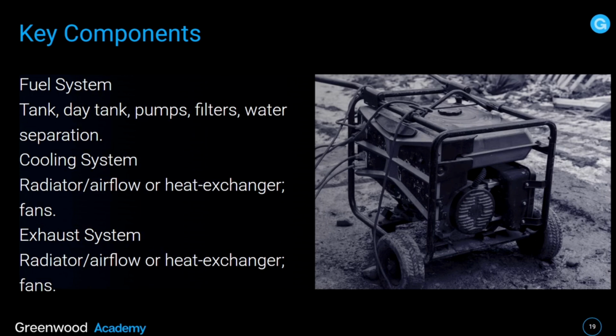Now, all these things have to be taken into consideration. One, when selecting what is the most effective GENSET for your application. And two, the most effective GENSET also depends on where it's going and where the exhaust is actually going. It's a really important point, especially when it comes to off-grid scenarios where you don't want to foul any kind of water tanks that may be the primary or only source of water for the occupants. It's a really important point. You have to take into consideration prevailing winds and where the actual diesel exhaust is going to go. Let's get back to it.